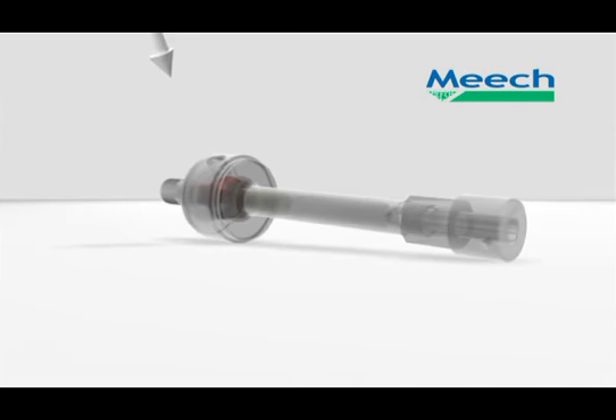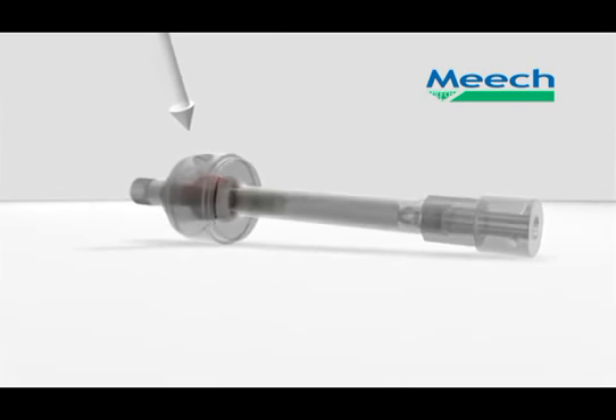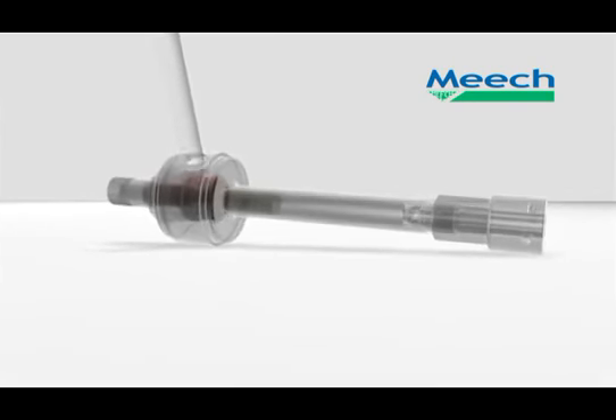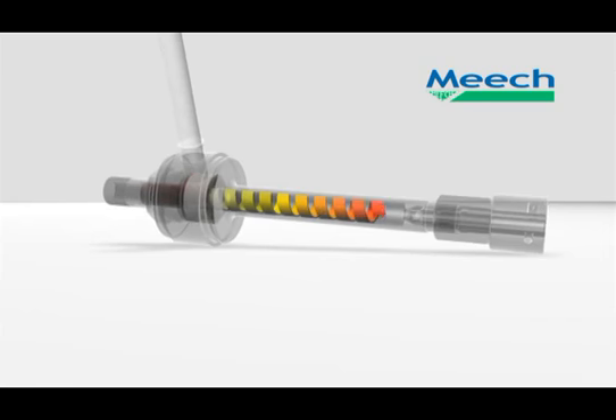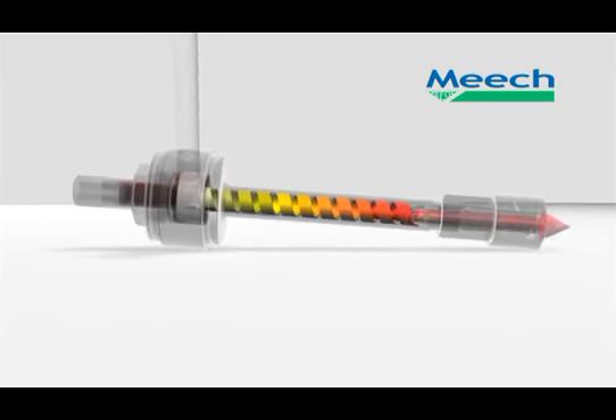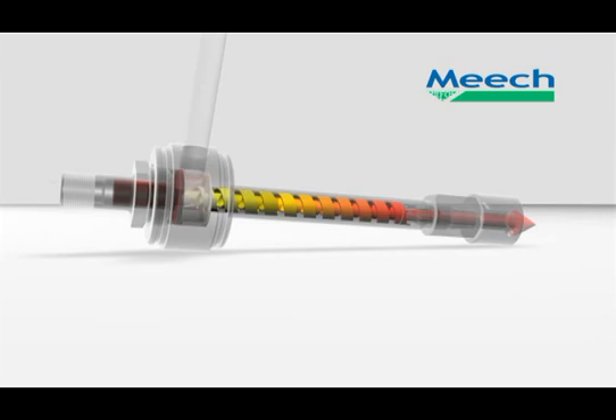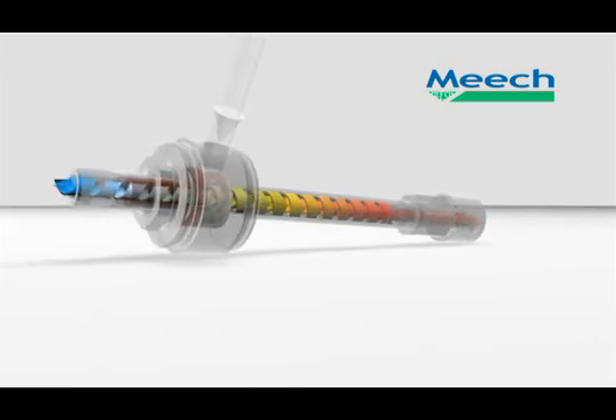So, how do they work? As the animation shows, compressed air enters the spin chamber. This causes the column of air inside the tube to rotate at speeds up to 1 million RPM. The air at the outside of the column, moving very fast, has a lot of energy and is hot. The air at the centre of the column, moving relatively slowly, has little energy and is cold.